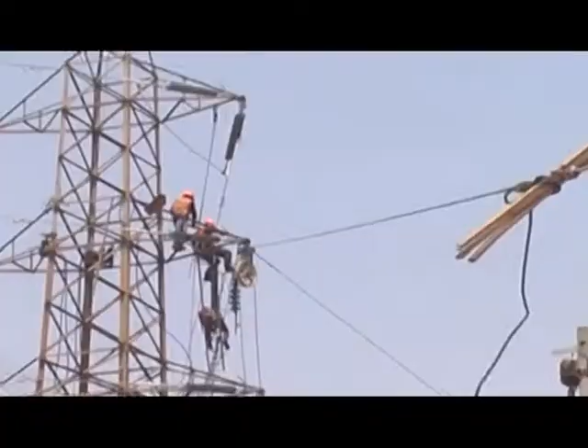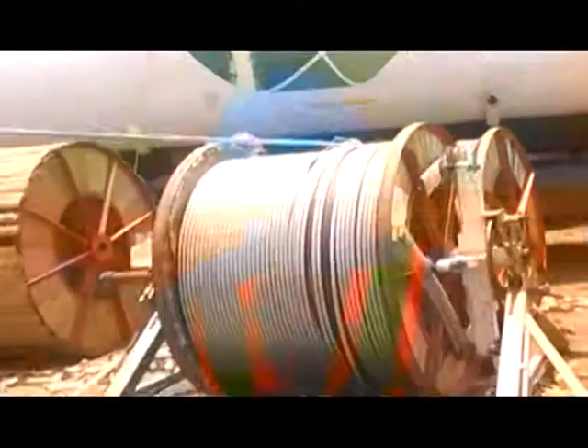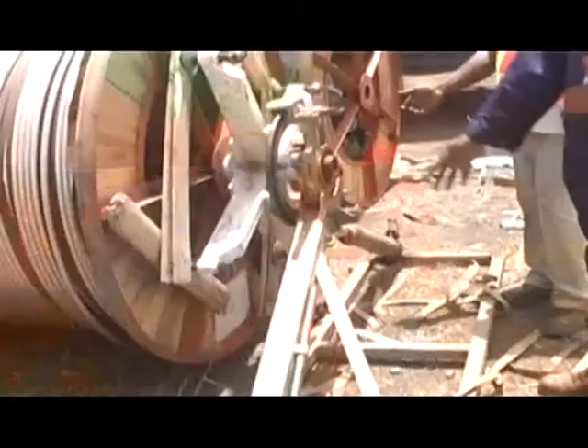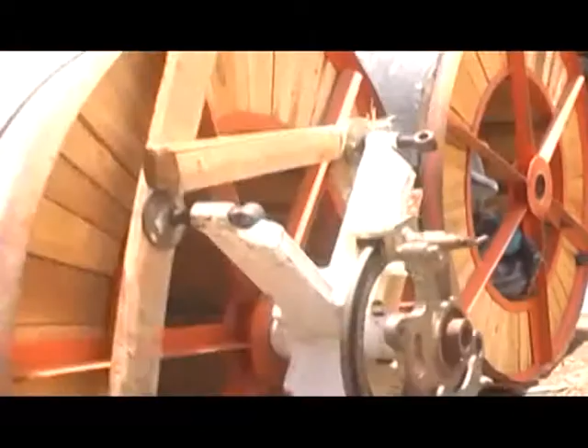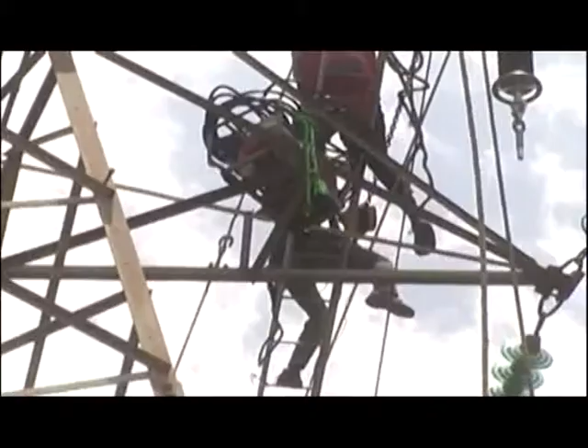The capacity of the line as it is now is about 120 megawatts, but this new conductor can give 240 megawatts — twice what was there before. The advantage is that you do not need to construct a new line between here and the power station; the old towers are reused with new conductor, giving twice the previous capacity.